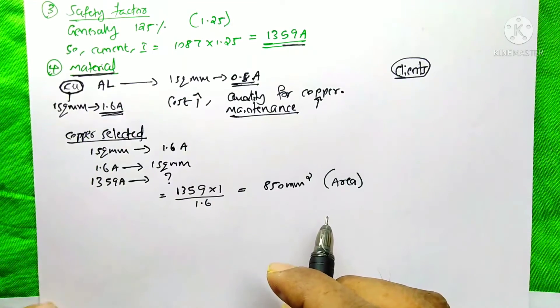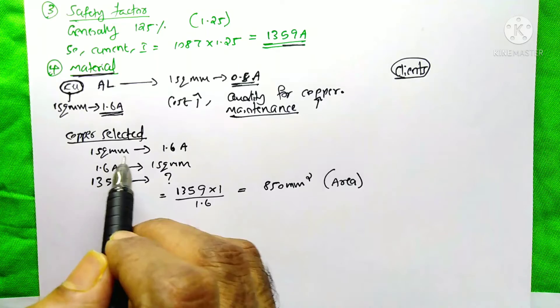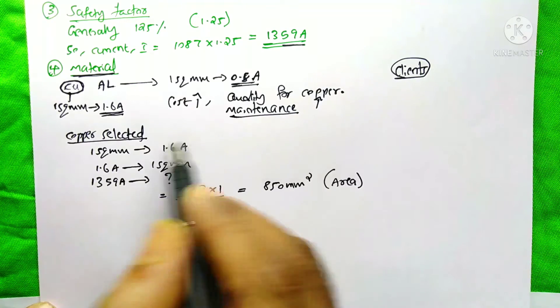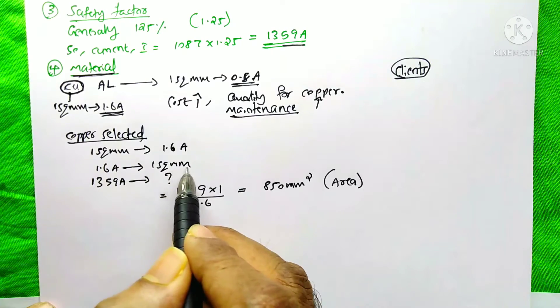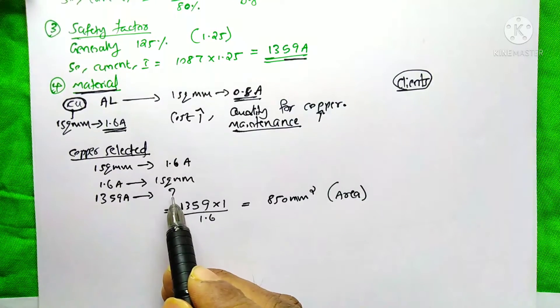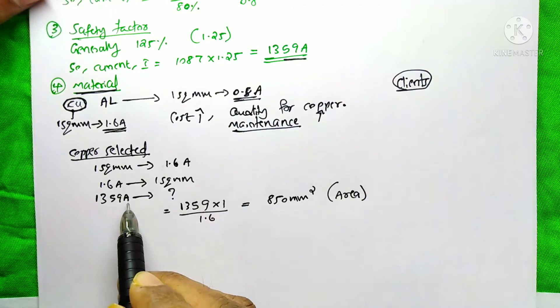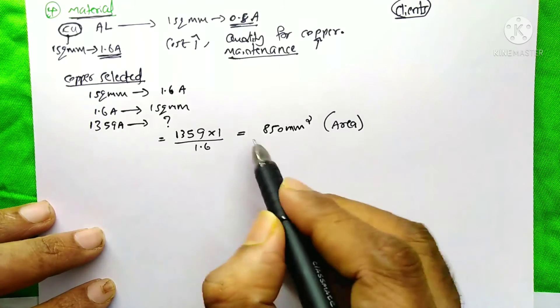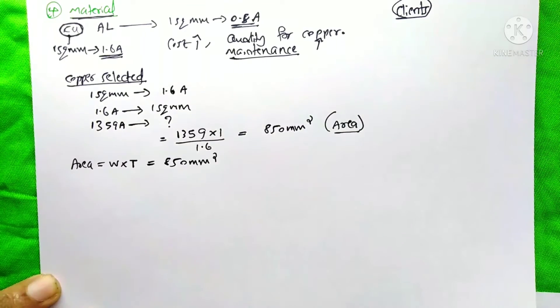We should convince our client to use copper rather than aluminum. In our example I selected copper. Since 1 mm² of copper carries 1.6 amps, we reverse it: to carry 1359 amps, we need 1359 × (1/1.6) = 850 mm² — that is the required cross-sectional area.